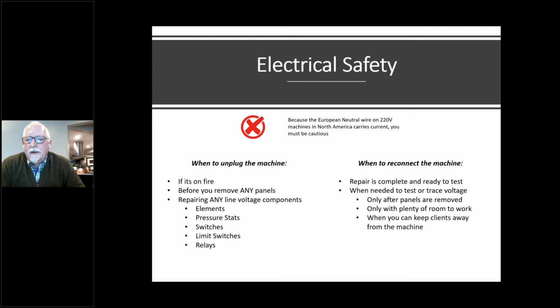And while you're repairing any line voltage components, that means elements, pressure switches, limit switches, relays, anything that's got high current going to it, sometimes you can trust the switch, sometimes you can't. There's going to be voltage in there at some point unless you just unplug the machine.